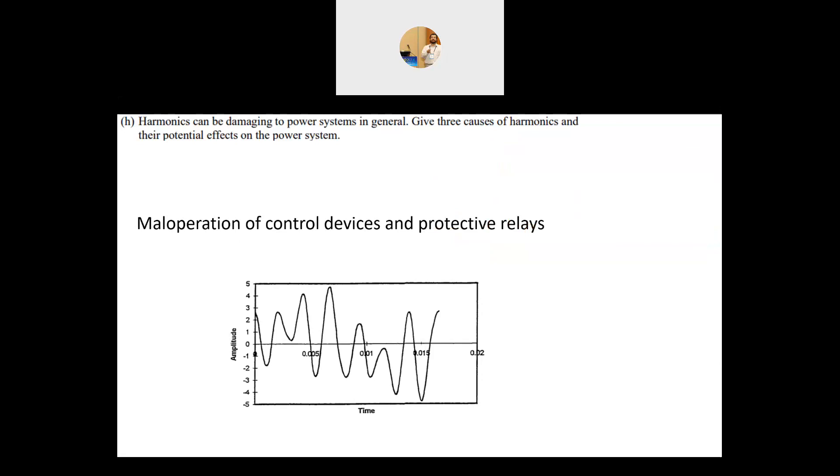How does this impact the power system? The first effect is maloperation of control devices and protection relays. This highly distorted current can have what we call multi-zero crossings. When you have such highly distorted current, it will cause maloperation of control devices or protection relays. They will misunderstand the signal and might open or close certain circuits that they're not supposed to.